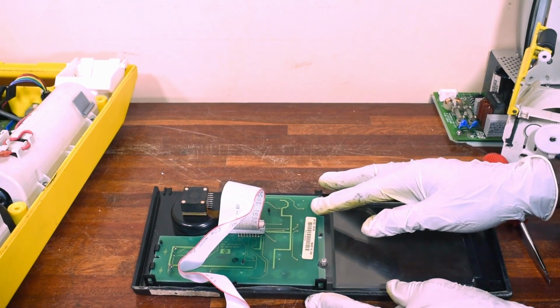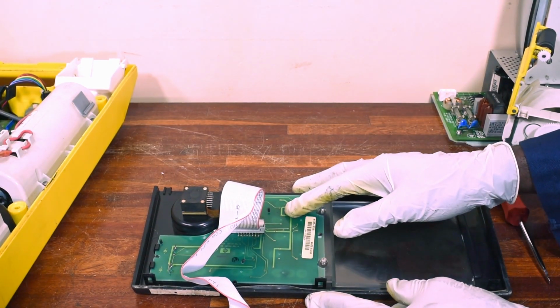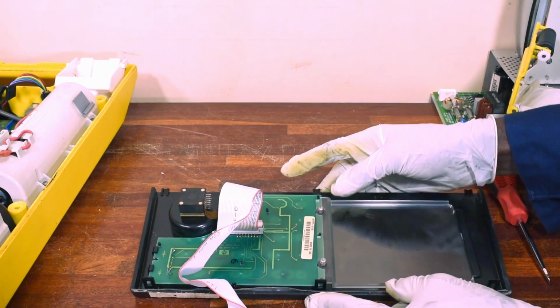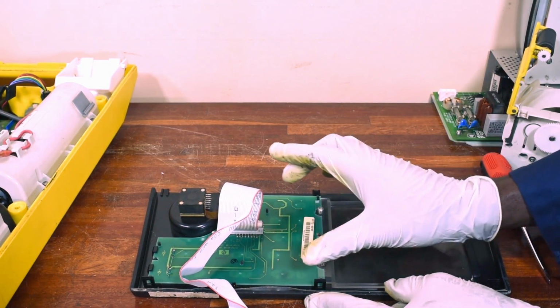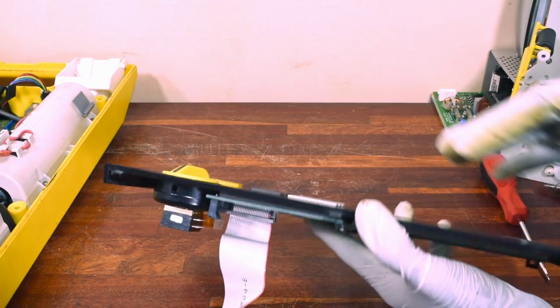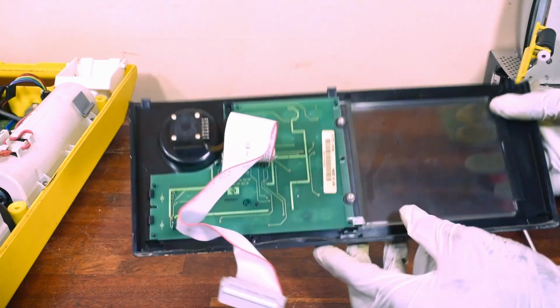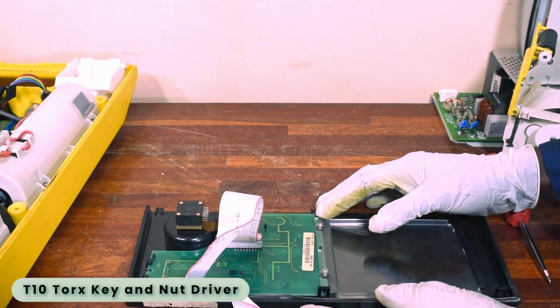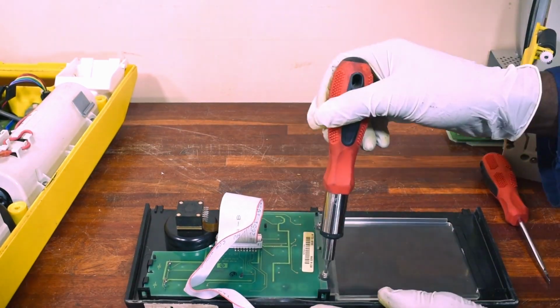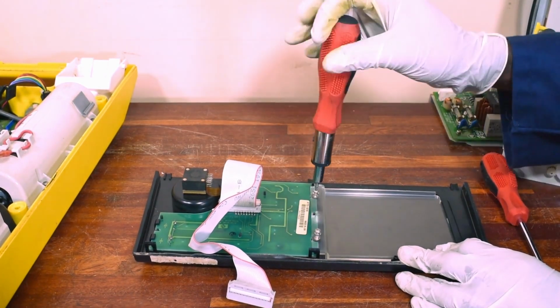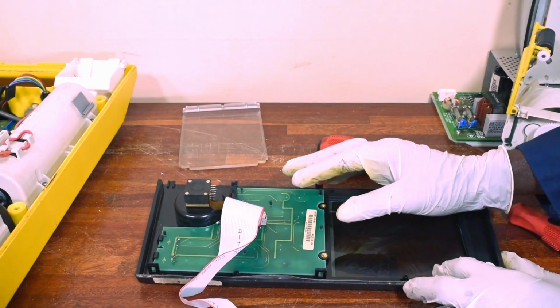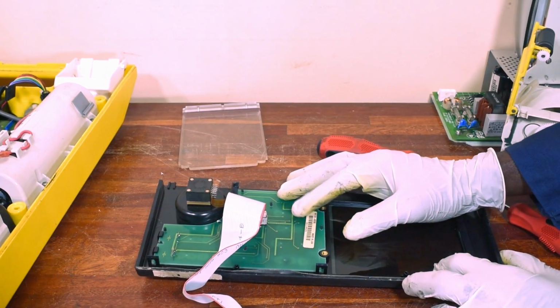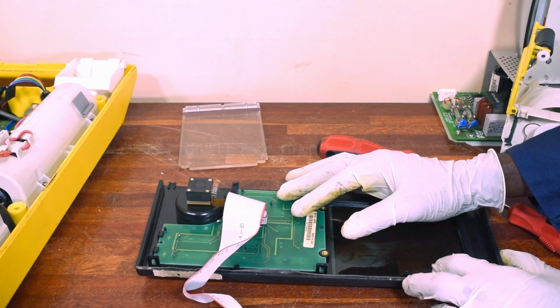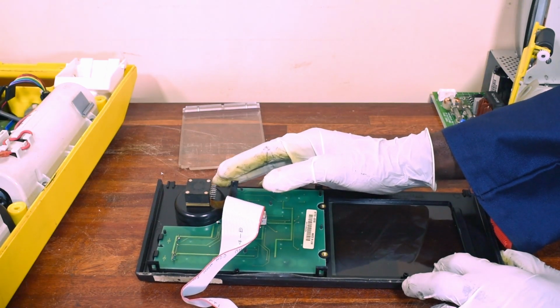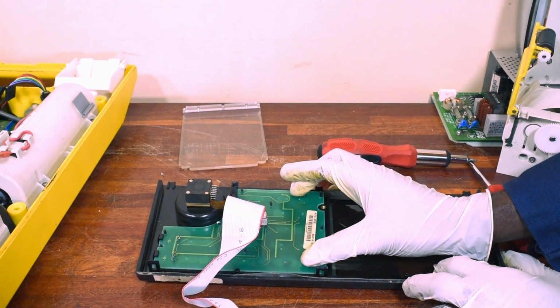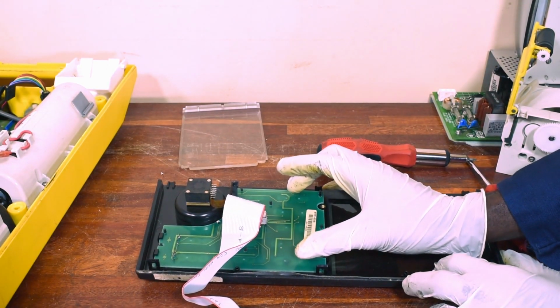Next, there are 2 Torx screws that secure the key panel circuit board, the key pads, the plastic rings, the bezel securing the circuit board, as well as the key labels. To remove these screws, I will use a Torx T10 key and a nut driver. The key panel circuit board supports push-button switches and LED indicators. It is interfaced with the energy select control by a flex cable. To replace this board, you will need to disconnect this connector using a flathead screwdriver.